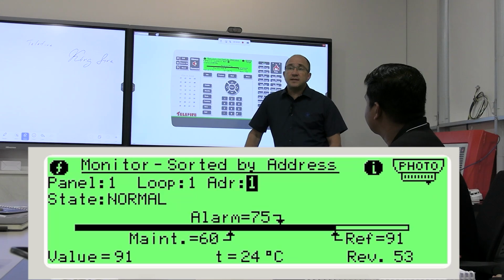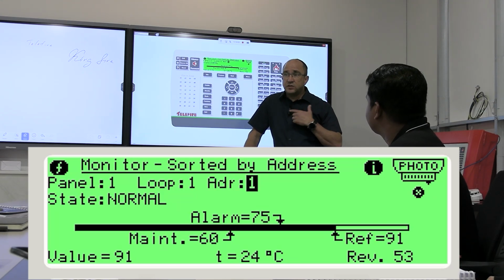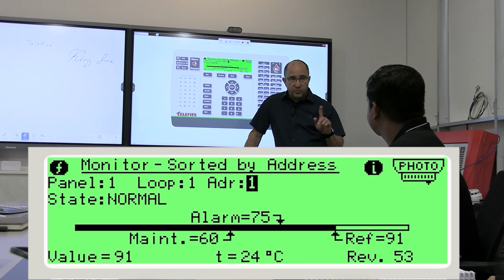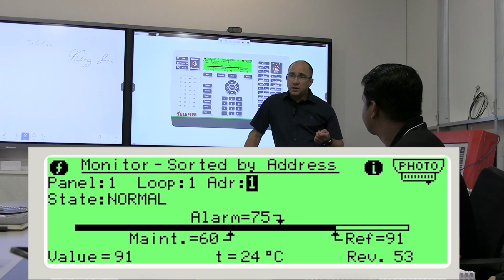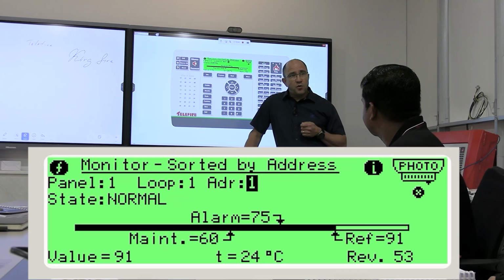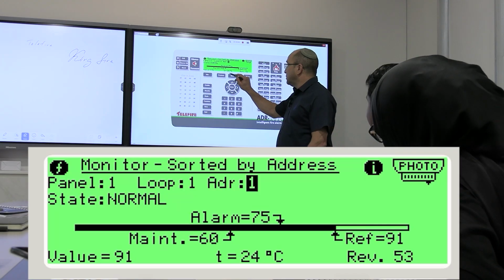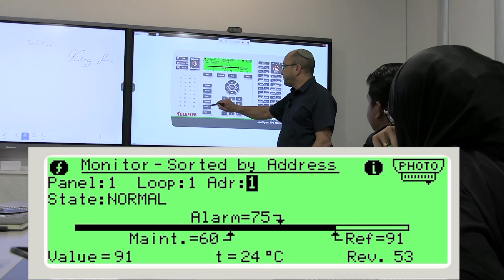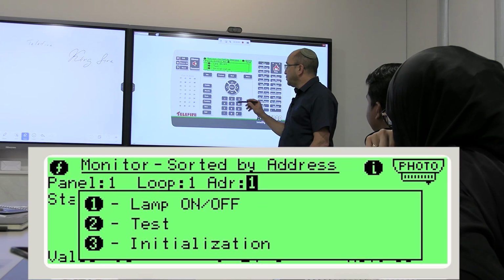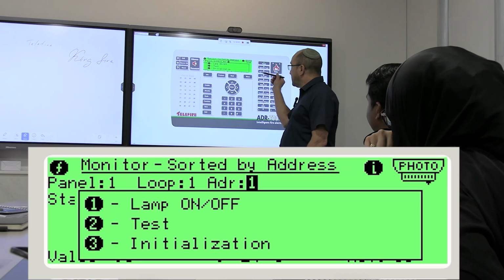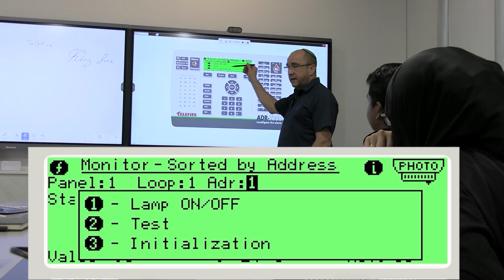I would like to test the detector, the CPU inside, to see if it's okay. I can take your magnet that you didn't bring yet because we haven't gone out yet, or I can give a command, check. I'll go to function and number 2. Please notice and see the graph, the bar playing.